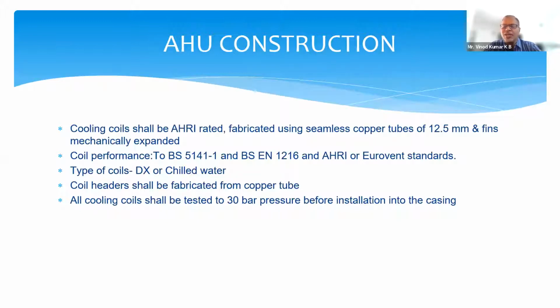Now here again, the vendors go for low cost copper tubes which are lesser in thickness, and the number of fins are also spaced at a wider space. The spacing of the fins as well as the copper tubes enhances your AHU performance in terms of giving you the correct cooling or adequate cooling, at the same time not wasting energy. If your coil is not correct, what happens? The cold refrigerant or the cold water will come and go. Heat exchange will not happen. Now, what is the actual intention of heat exchange? The heat exchange is basically to cool the air. That cold air has to come to your premises, which is your theater or ICU.